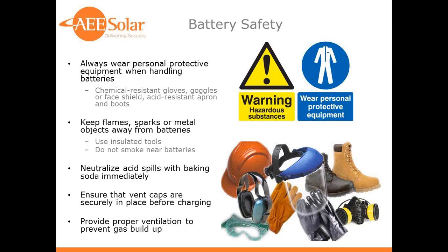Essentially, the hydrogen will try to get out into the atmosphere because it wants to go up in the upper atmosphere anyway, being very light, as opposed to something like, say, propane gas, which is very heavy and would sit and pool on the floor. Hydrogen doesn't do that. It tries to escape through the topmost place. But make sure you have good ventilation. You also can deal with hydrogen sulfide gas, which is poisonous. So it's that rotten egg smell. You don't want to have too much of that because that is poisonous.